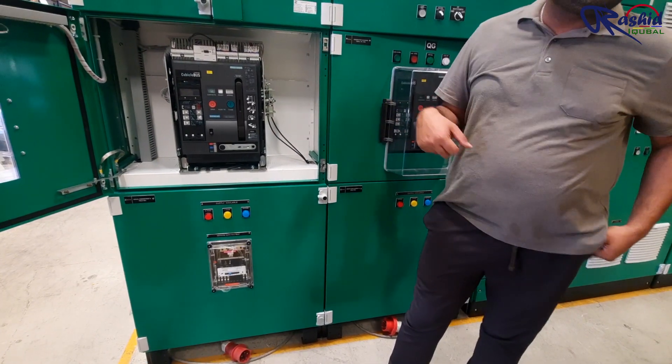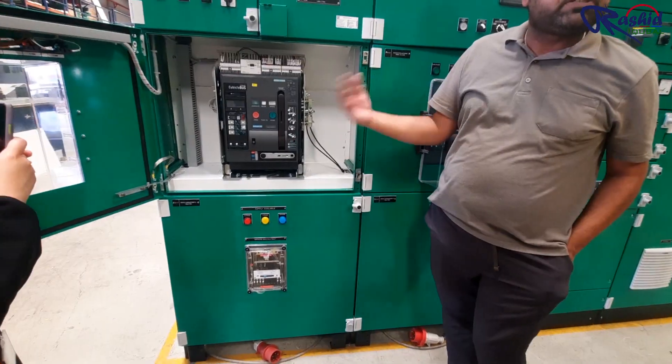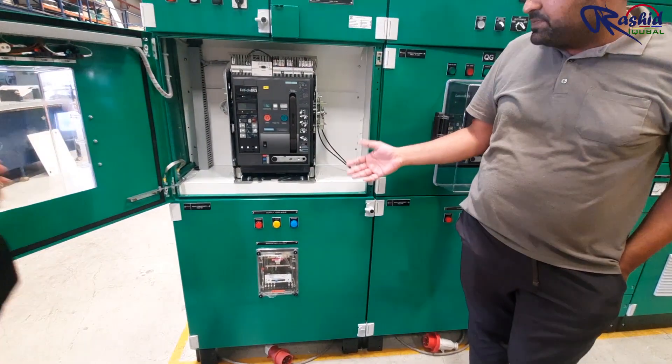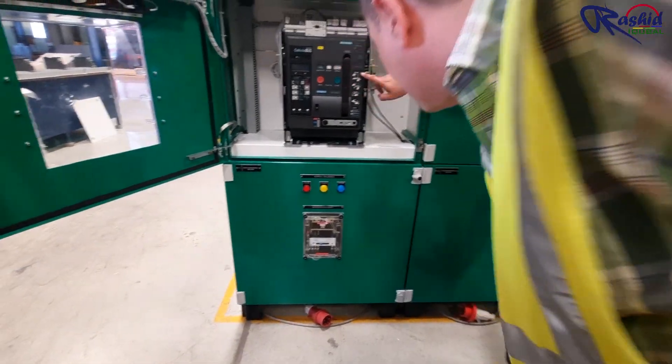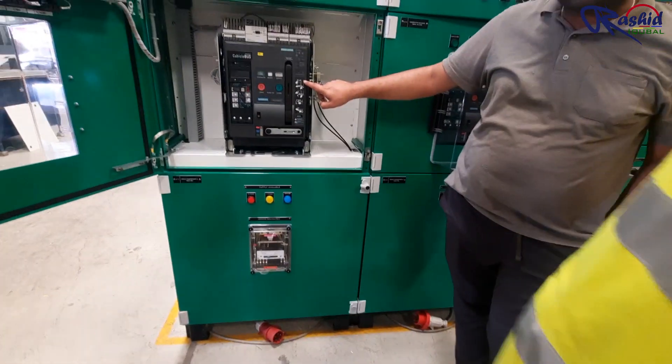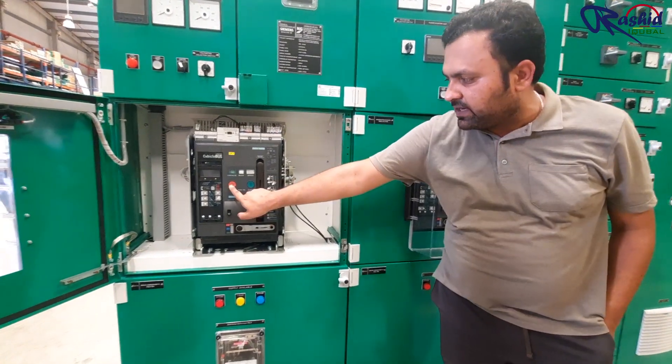Here is the procedure for how you can rack in and rack out the ACB. You also have a counter showing how many operations the breaker has performed. The sequence of operation: first you need to ensure that your breaker is off — the indicator is pointing there showing the breaker is open.